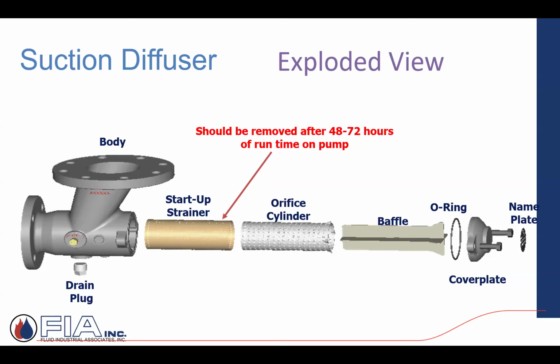But on the construction site, there's sediment, there's stuff in the system. We want to use this startup strainer to maybe catch as much stuff as we can before it gets to the seals of the pump and damages them, or even the impeller.